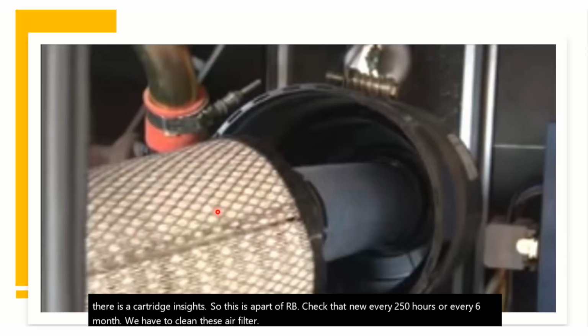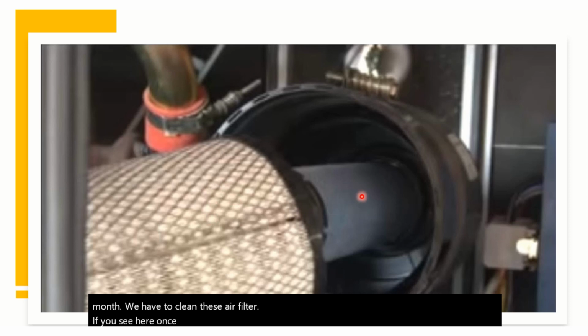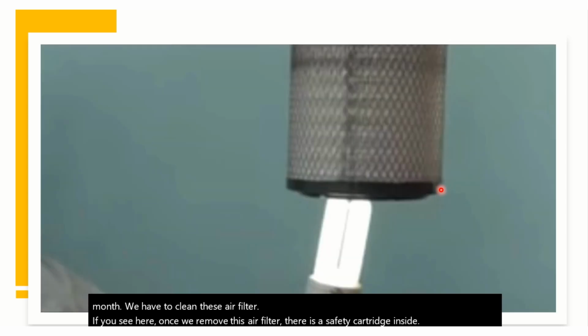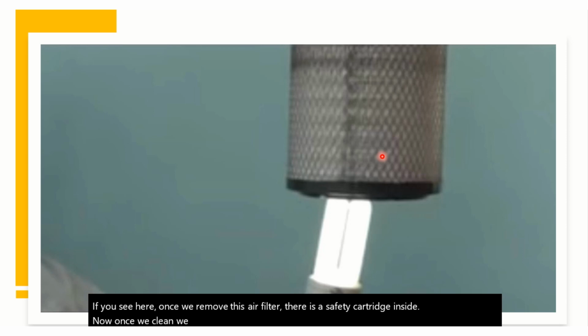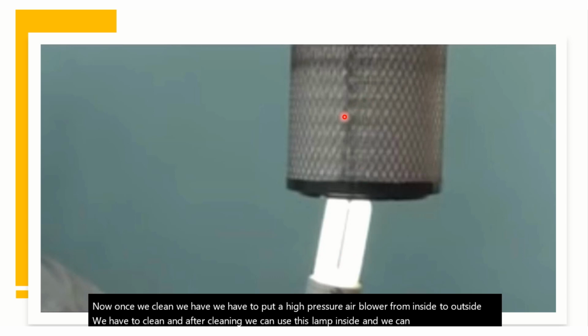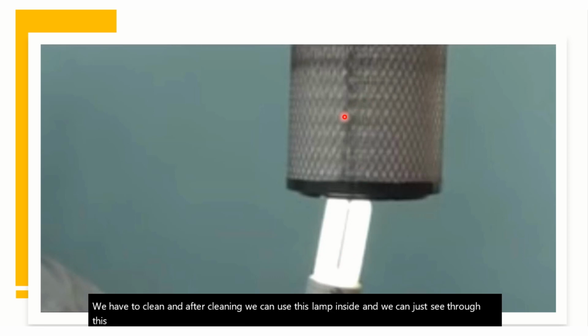If you see here, once we remove this air filter, there is a safety cartridge inside. Once we clean it, we have to use a high pressure air blower from inside to outside. After cleaning, we can use a lamp inside and look through the filter, and if we find any rupture or any damage, we have to replace it.